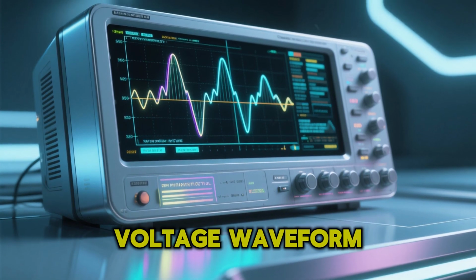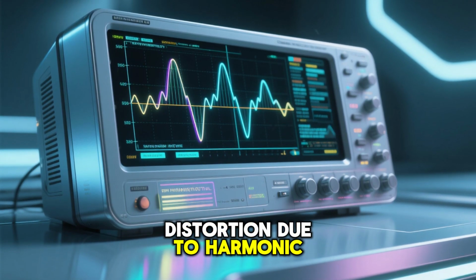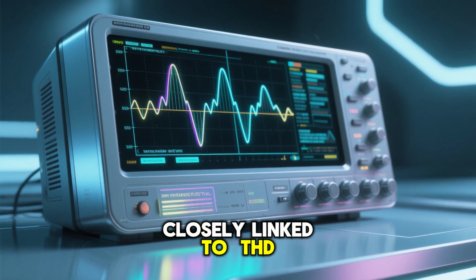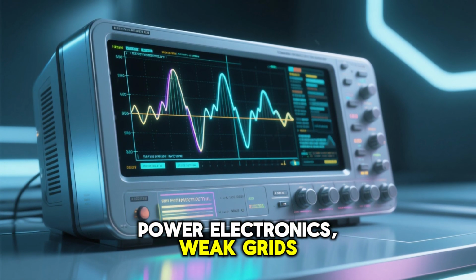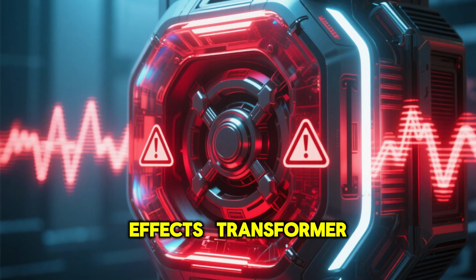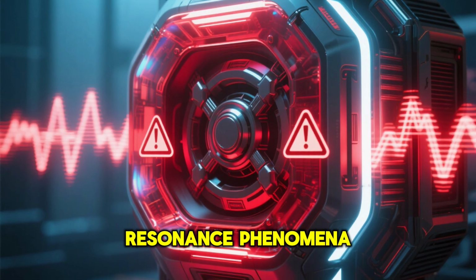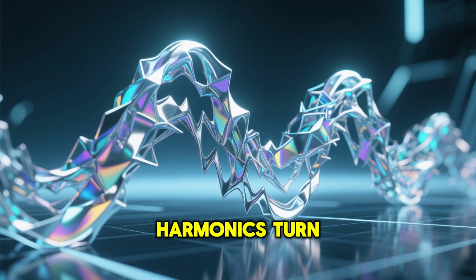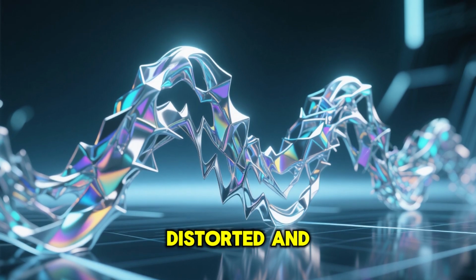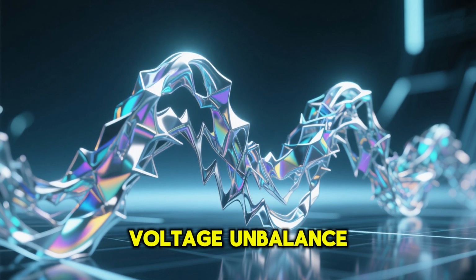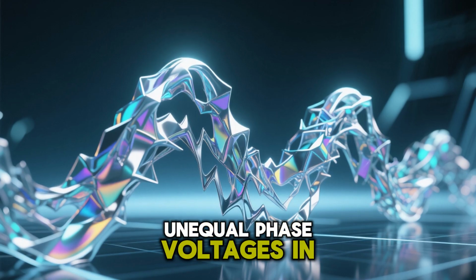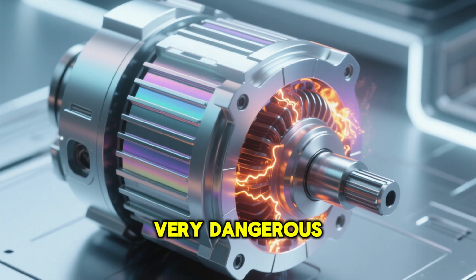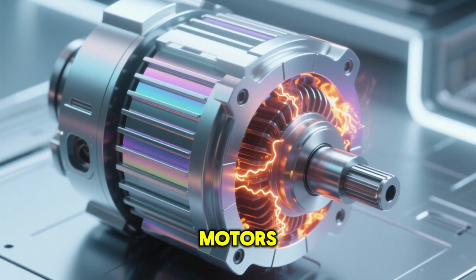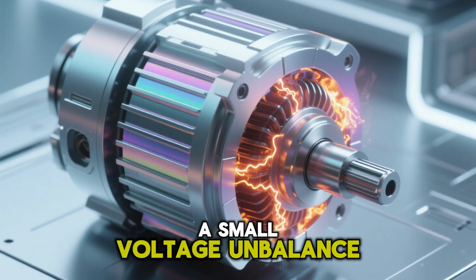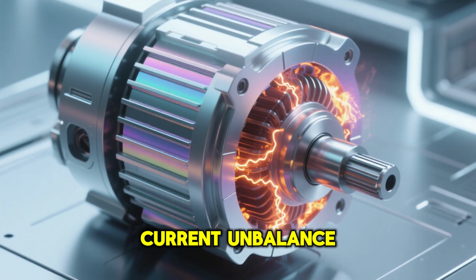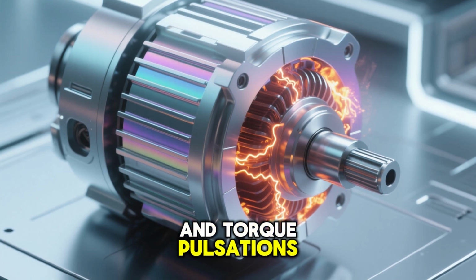Voltage harmonics. Voltage waveform distortion due to harmonic currents, closely linked to THD, power electronics, weak grids. Effects: transformer overheating, resonance phenomena, protection malfunction. Harmonics turn a clean sine wave into a distorted and dangerous signal. Voltage unbalance. Unequal phase voltages in a three-phase system. Very dangerous for induction motors, rotating machines. A small voltage unbalance can cause a large current unbalance, leading to overheating and torque pulsations.